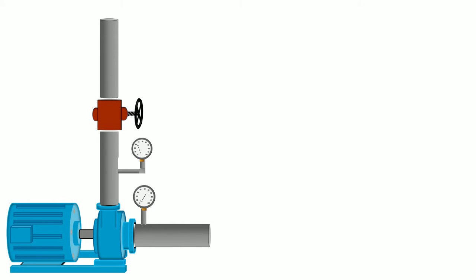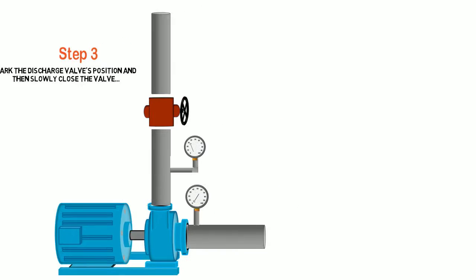Next step, we're actually going to go to the mechanical room. We're going to go to our pump and we are going to shut the discharge valve slowly while the pump is running. First, we're going to mark the position it was in before we closed it, because we want to return it to that position when we're done.